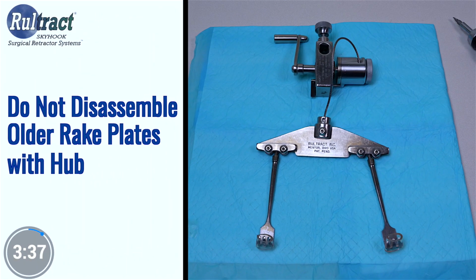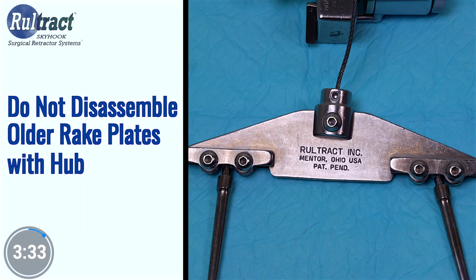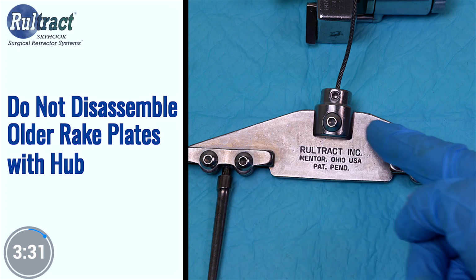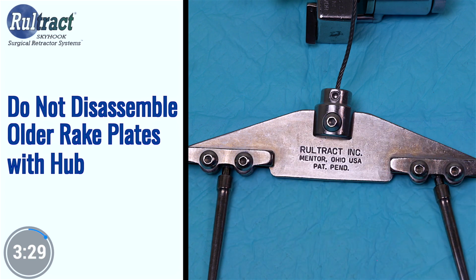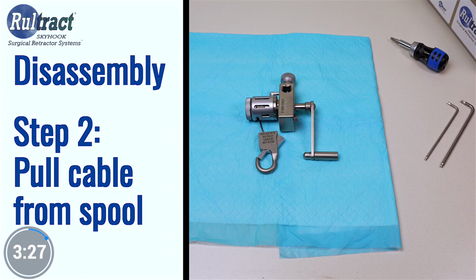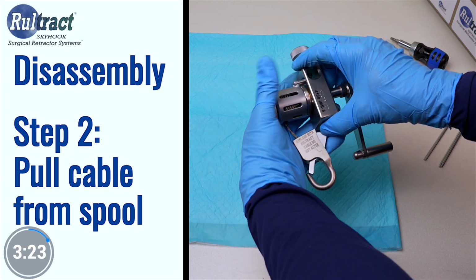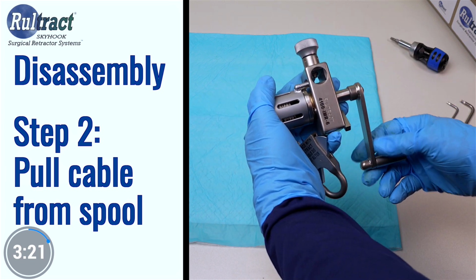Some of the older Rultract rake plates have the cable attached to a hub which is attached to the rake plate like this. If you have an older system like this, you will not remove the rake plate from the hub. Pull the cable from the spool. You do not want to use the crank handle to unwind the cable from the spool because the cable can get kinked inside the spool cap.